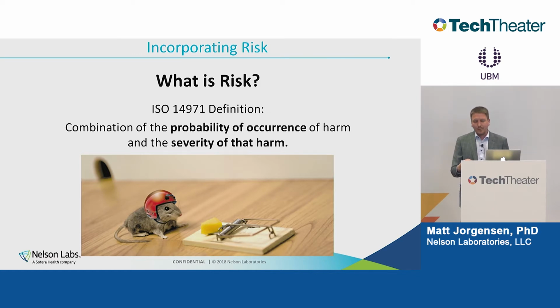For example, if a potential risk is that since the device would be commonly used in California there could be an earthquake, and if there was an earthquake, a lamp would fall off and break off part of the device - while that might technically be a risk, the probability of that happening is so low that maybe we don't need to address that particular mode of failure for the device.